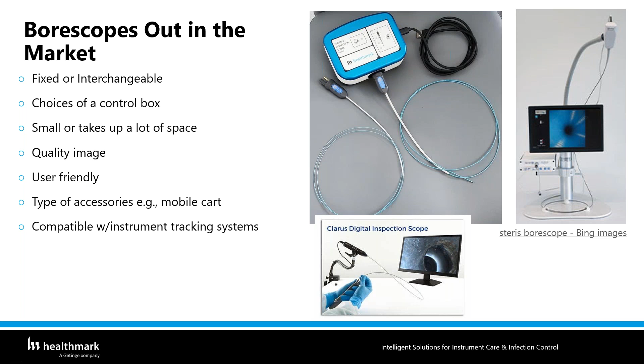For example, these are some borescopes in the market. Here you have a Steris that has different lengths of wires. We have Healthmark, and here we have another one from Clarus that gives you more flexibility of changing the catheter if you need different sizes. For example, for some of the shavers you need a 60 centimeter line, versus an endoscope, where you may need 110 centimeter or even 210 centimeter line to go through the whole length of the endoscope. So these are all available, and there are many choices, from really tiny, less than 1 millimeter diameter, to higher quality, 2 millimeter or so.